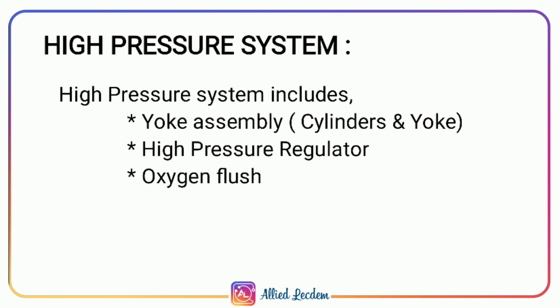The high pressure system of the Boyle's machine includes the yoke assembly, cylinders and yoke, high pressure regulator, and oxygen flush.